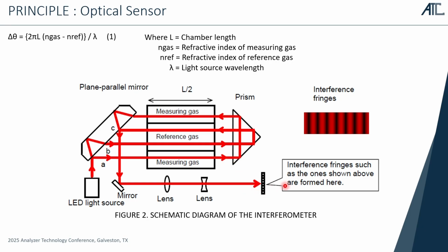Oh, and then the light source of this sensor is LED, so its light lasts for a very long period. And since the wavelength of the light source and the chamber length in the sensor are stable, there is no sensitivity change after the calibration at the factory.